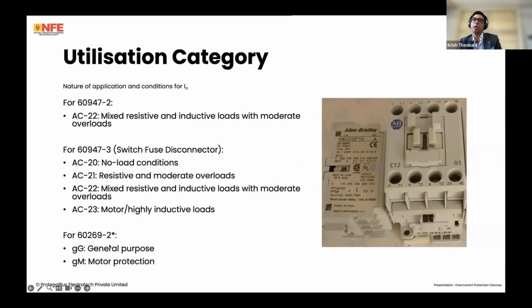Okay, so utilization categories are quite an interesting subject. It is basically the nature of current and nature of loads that the devices are switching. So when it comes to circuit breakers, like I said, these are only given for 60947 Part 2 circuit breakers, and then for switch fuse disconnectors, and there are some other devices as well. Generally speaking, for circuit breakers these are given for AC22, if you refer to the 60947 series. This is basically a mixed resistive and inductive load with moderate overload. This is your everyday domestic situation and possibly some commercial situations.